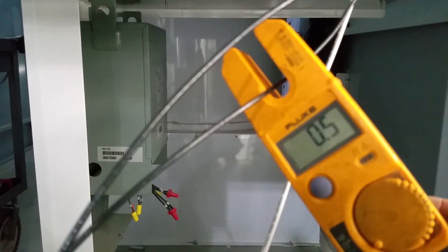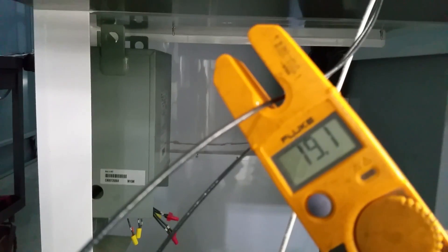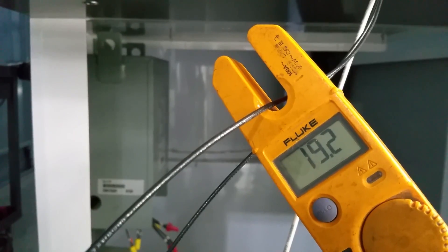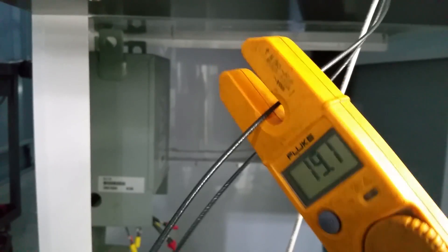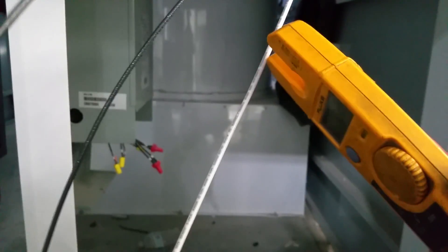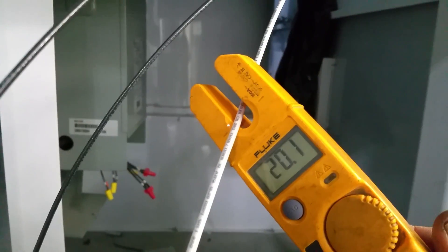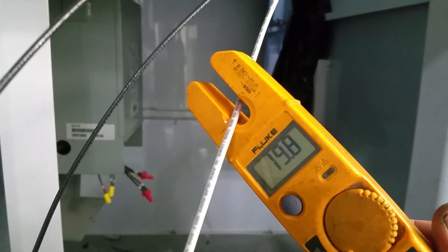Now we're going to fire the first half of the lights. Now we've got one hot and one not. So that's half an amp, a little bit of transient voltage. Here we're talking about 19 amp and our neutral load is almost 20.